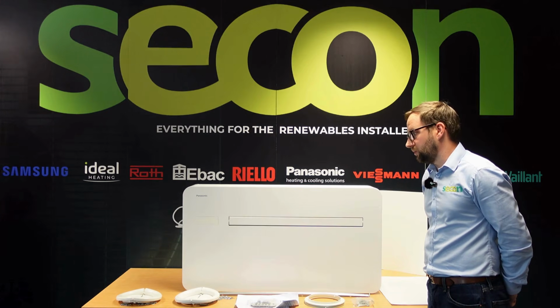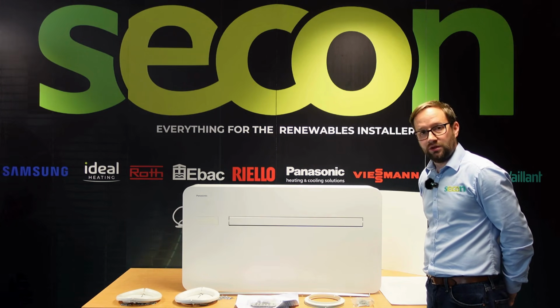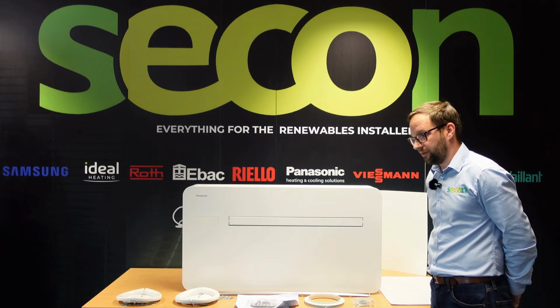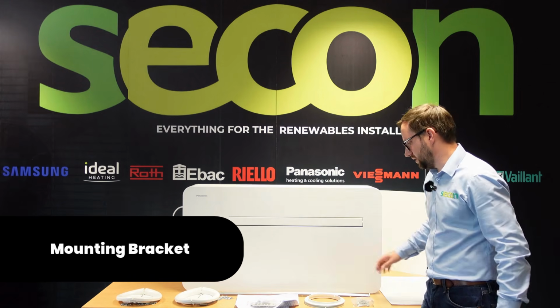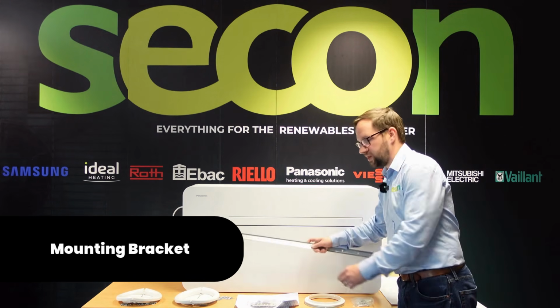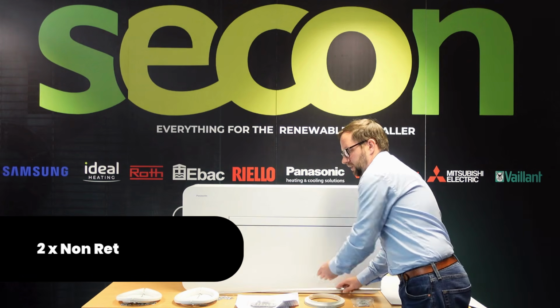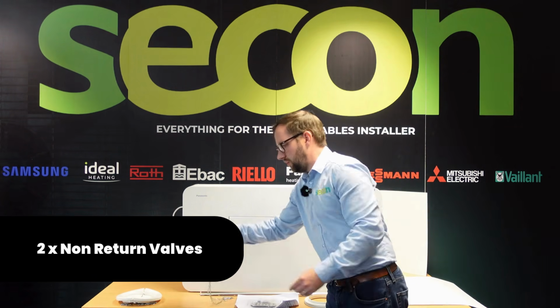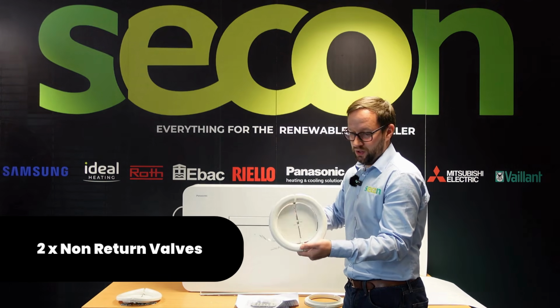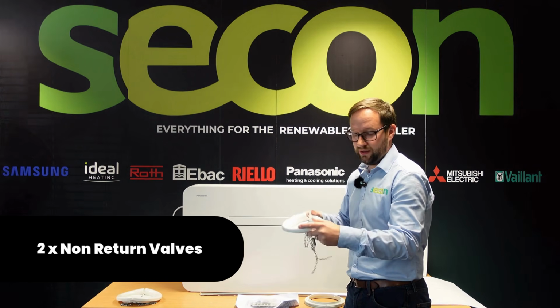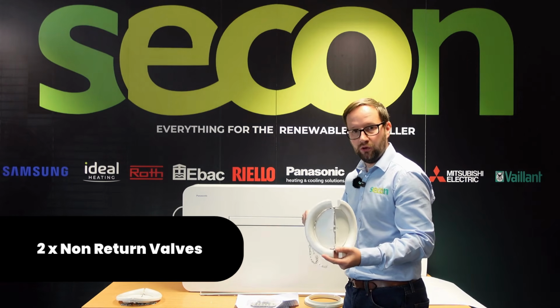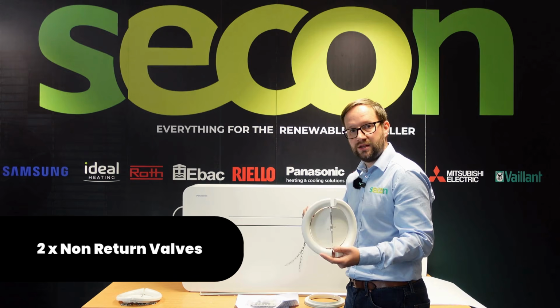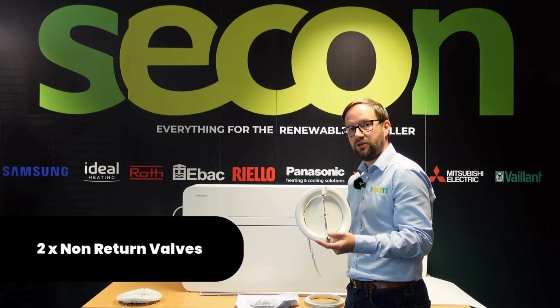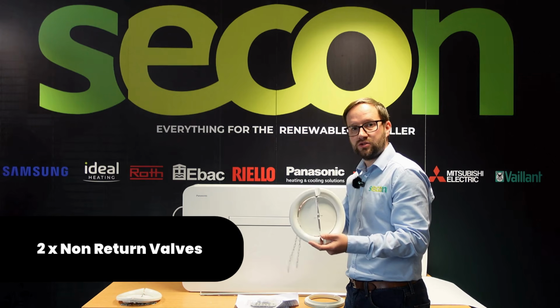Once you unpackage your RAC Solo unit, you'll find there are a number of accessories included in the box with the unit. You get your mounting bracket, and you get 2 non-return valves. These are designed so that they can be threaded through the ductwork and then pulled back from the inside, allowing you to install this in a high-rise situation without accessing the outside of the building.